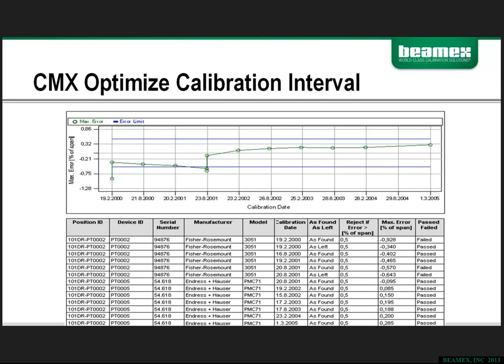All right. And with this slide, this gives you a little broader understanding. Now it's including the graphical form as well as the numerical form for this particular device. And this is actually a position ID. If you look at the left, it shows you 101DR-PT0002. Initially they used a Fisher-Rosemount 3051 to fill the function for this particular device, and it gives you the calibration date, whether the data that's been recorded was as found or as left. It would basically be rejected or considered a failure if the error was greater than 0.5% of span. So if you look at this very first error, you're reading 0.928, which is almost 2 times the specified tolerance, which would be considered significant.